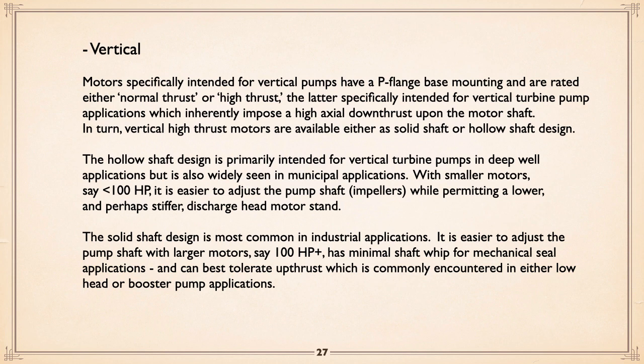They also can tolerate upthrust, and that can happen in a low head application or a booster pump application. If you get in a situation where it tries to turbine or whatever, it's not uncommon to get upthrust, where the shaft is trying to poke up. Solid shafts don't care much about that. It's a big issue if a shaft starts to unscrew. Upthrust is a problem with hollow shaft.